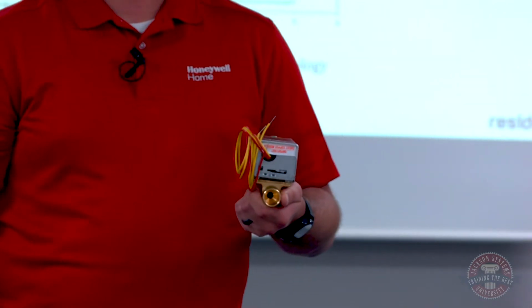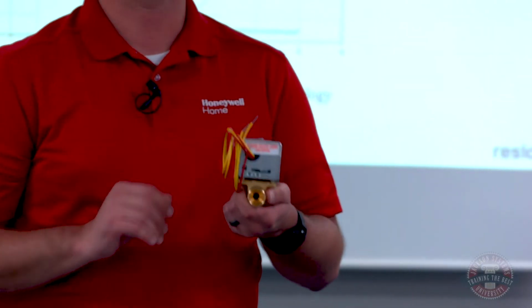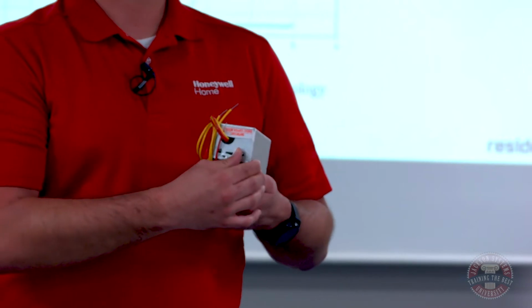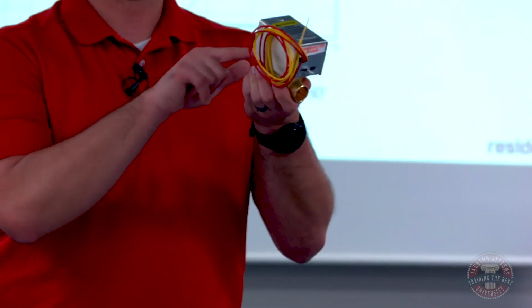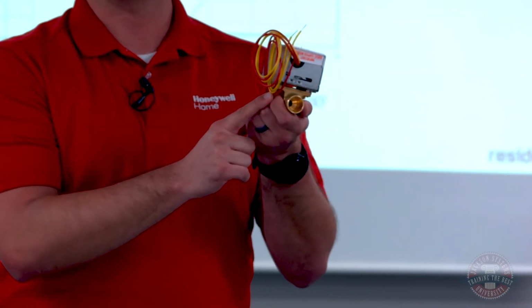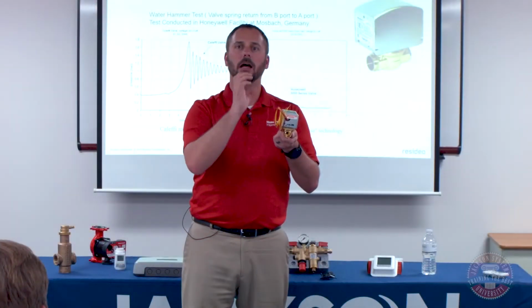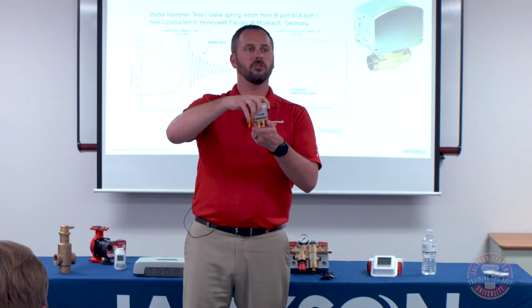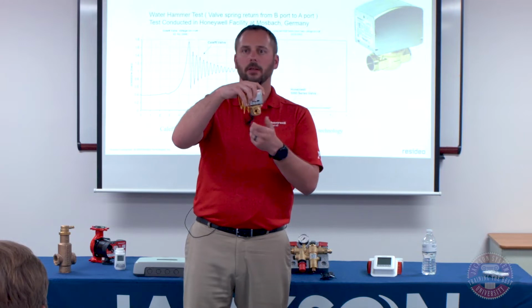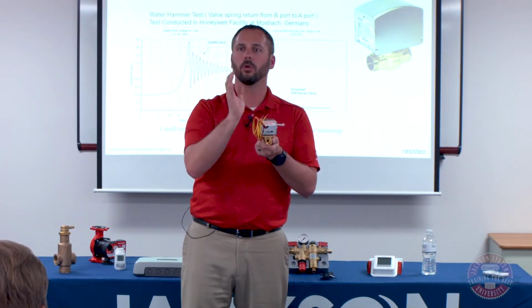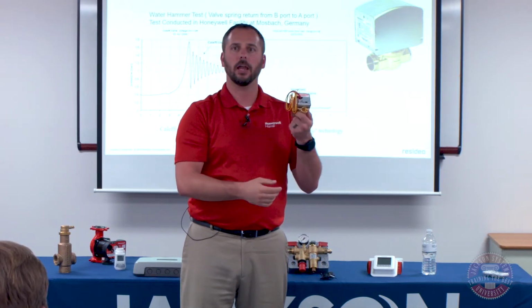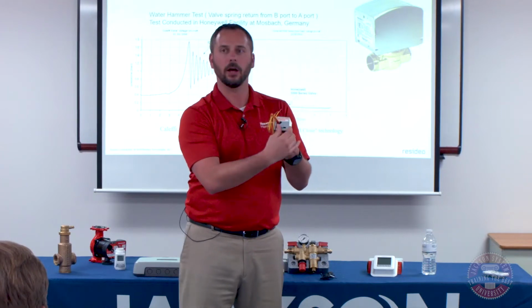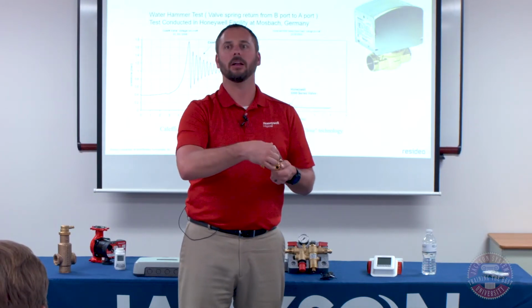The reason we do that is when you commission a job site, you have to purge, and you want to leave all your valves open. If you try to operate this when it's not screwed down securely to the valve body, the gear assembly does not line up properly. They're engineered so the gear assembly and the body have to be bolted together in order to line up. So if you took a handful of power heads not mounted and tried to operate them, they would act like they're stripped out.